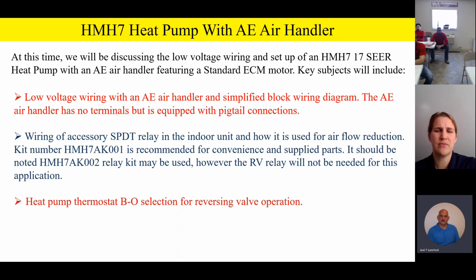These relay kits are utilized for airflow management. The other thing we want to make sure that you have, because this is a heat pump, is that your heat pump thermostat is configurable for B or O selection for reversing valve operation. Now, this is really important. You guys put this in your back pocket one more time.